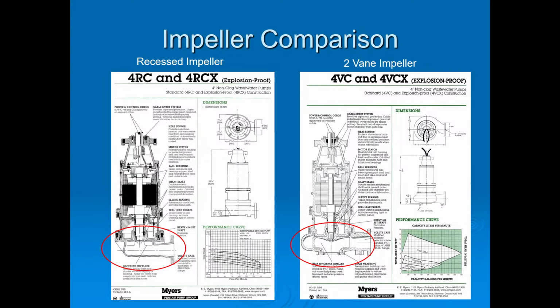The impeller on the right is a 2-vane impeller pump. The solids come up and go out through the 2 vanes, which are 180 degrees opposed from each other, so it's completely balanced from that perspective. You'll notice the one on the right has a wear ring. The one on the left has no wear ring, so it's not quite as efficient, but not as bad as you think. The one on the right is the most efficient pump available to pump wastewater, because it's like the oil rings in your car. It's a great application.